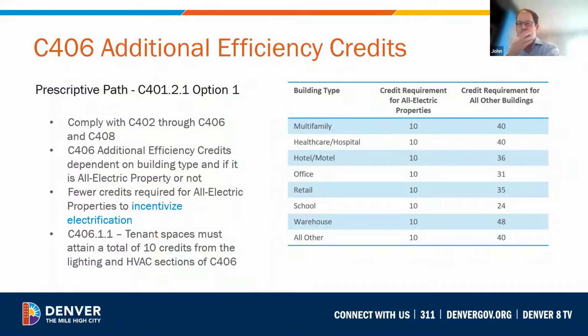Tenant spaces, additionally, must attain a total of 10 credits from the lighting and HVAC sections of C406. Note that this is higher than the 2021 IECC requirement of 5 credits. Projects meeting the requirements of C407 and using a performance approach option are exempt from the credit requirements. So these are only applicable to the prescriptive approach.